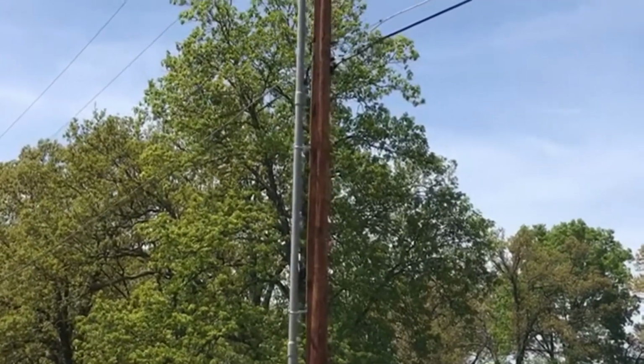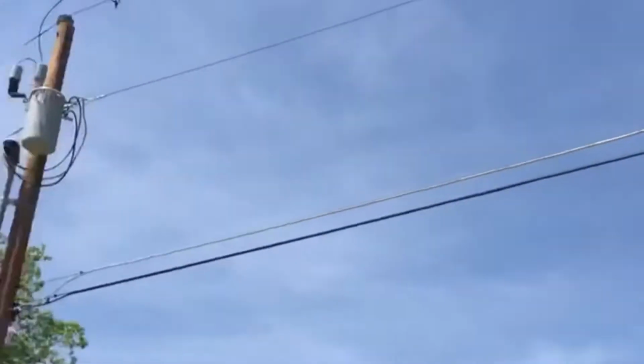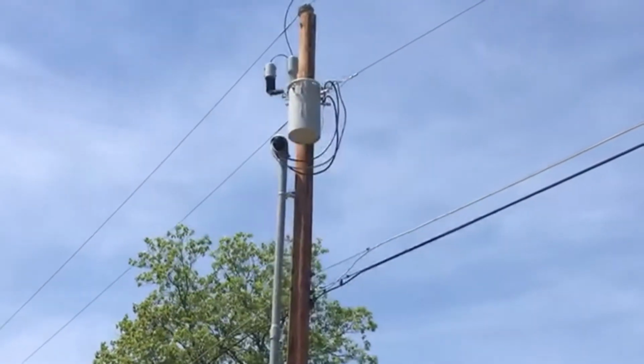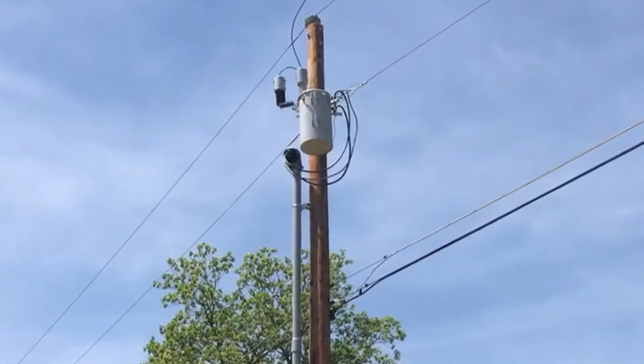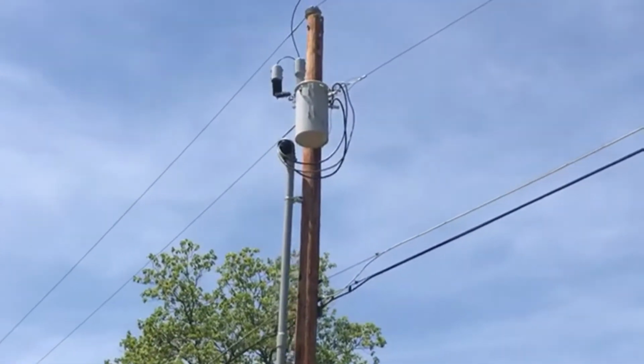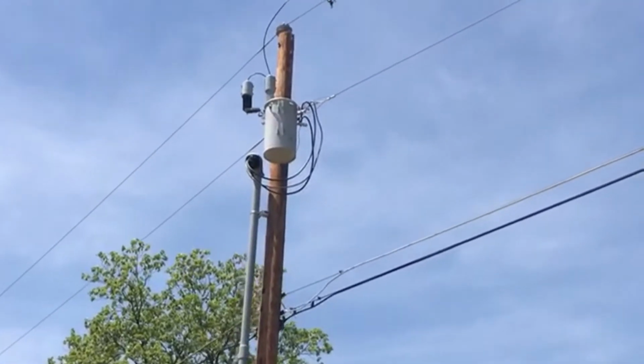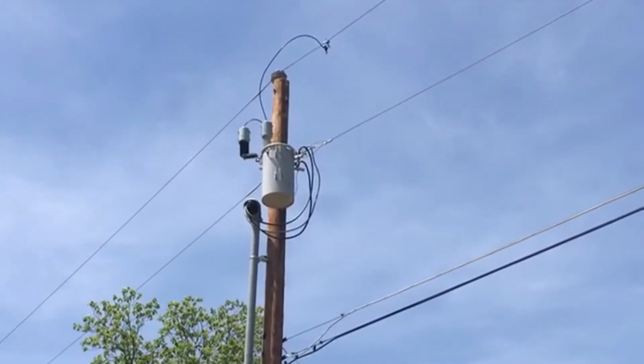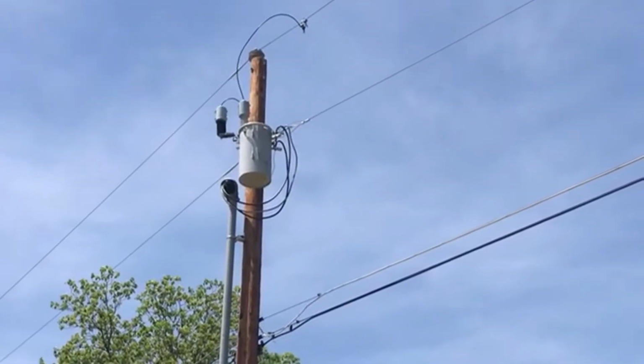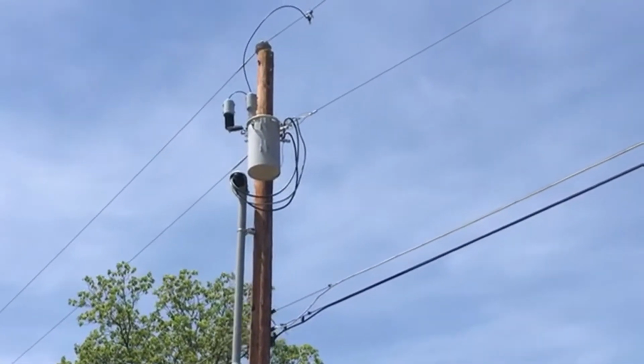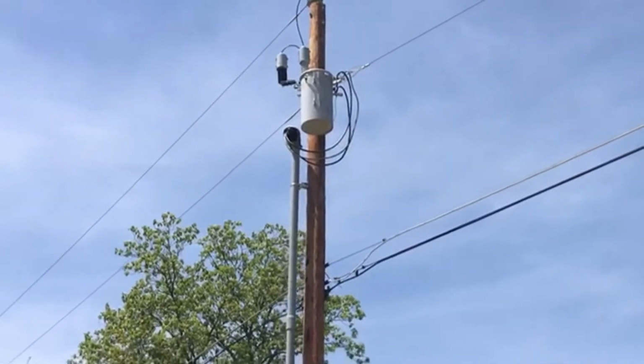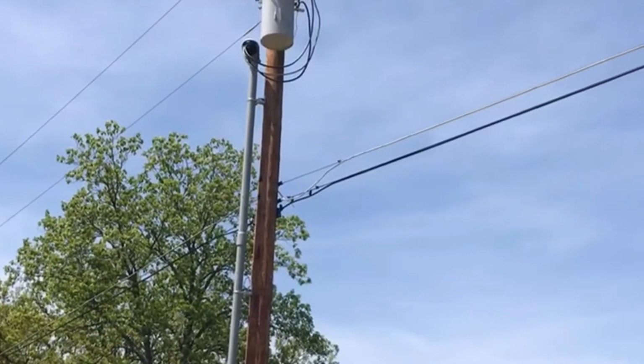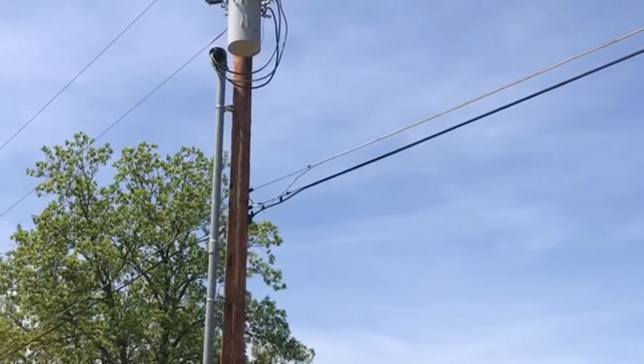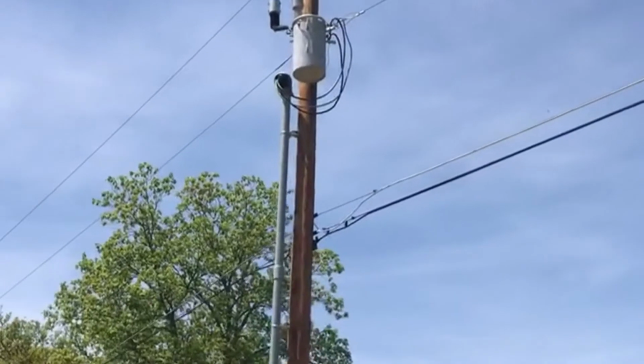So here we have the pole. These are your power lines from West Kentucky Rural Electric. The top line is your primary line. I think West Kentucky has 14,400 volts run through their primary. So there's one single primary at the top of this pole. The line below the primary, which is the second line from the top, is your neutral line. The bottom lines are the cable, telephone, and internet lines supplying this subdivision.